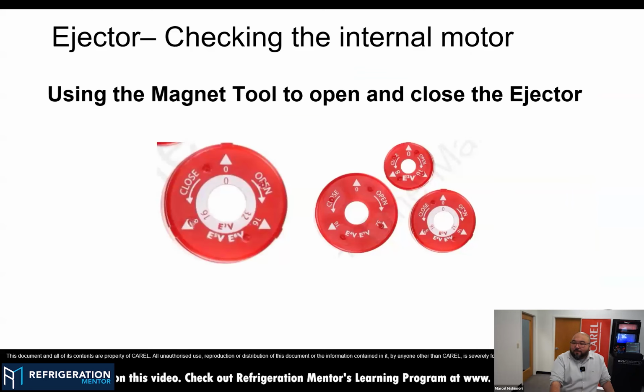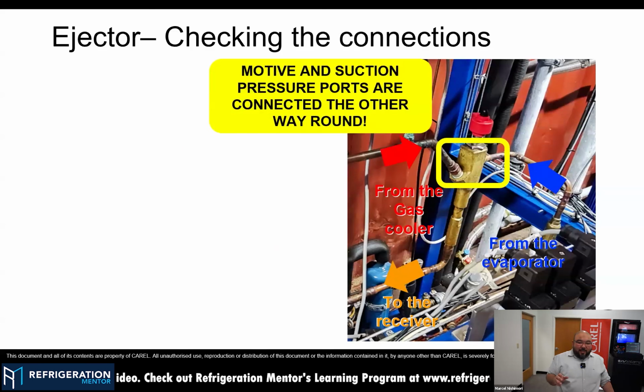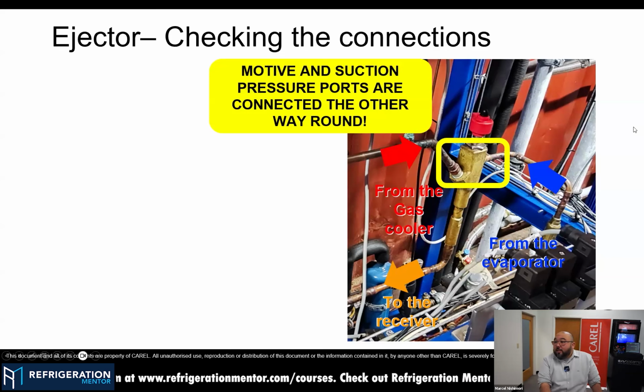So first things first, ejector position. Again, we have a three-way position, and this is just to show a picture of an installation where the customer was complaining that the ejector was not working, it was not regulating properly, and so on. If you see here, we had a wrong-way installation of the ports. So basically, they had the ejector installed in an incorrect way.